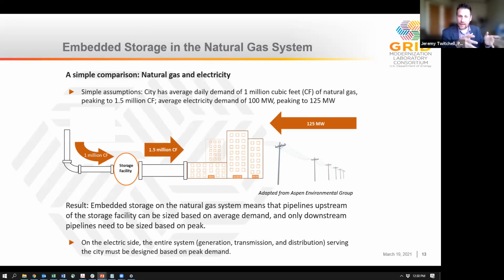On the gas side, by having that storage facility in the delivery system, the upstream portion of the pipe, everything leading into that storage facility can be sized based on average demand, only needing to meet that 1 million cubic feet. When demand is low, we fill up the storage facility, and when demand is high, we use it to meet demand. So the only part of the system that needs to be sized based on peak demand is that last mile, everything downstream of the storage facility, obviously more than a mile, just everything downstream of it.